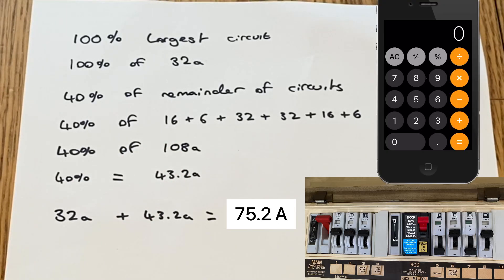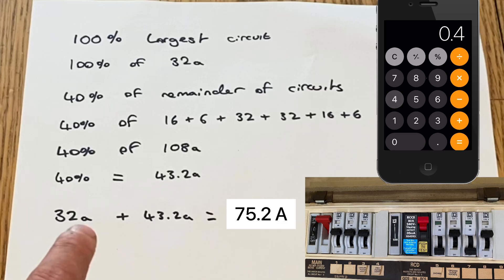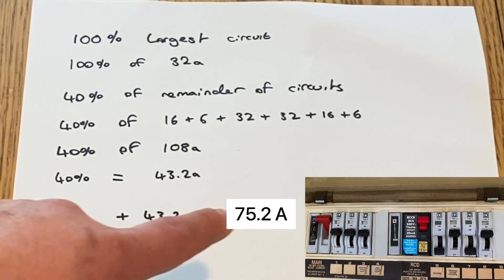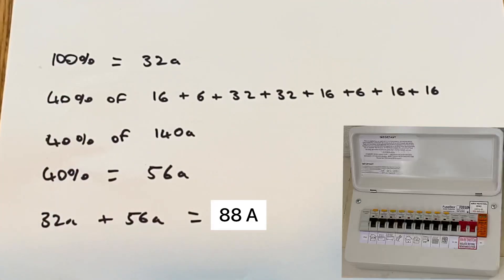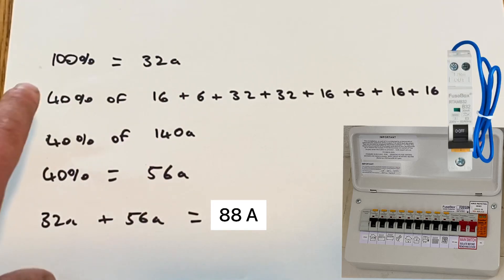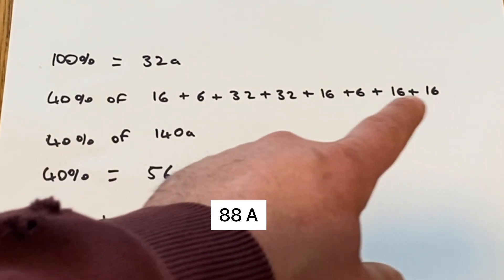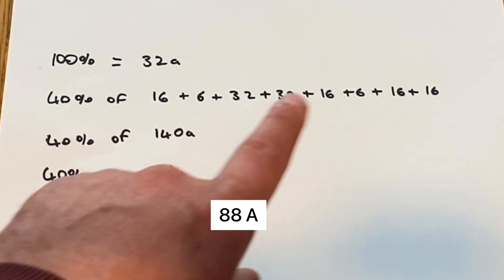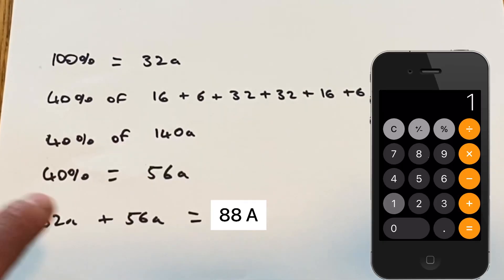For the new layout with the extra circuits, again we take 100% of the largest circuit, 40% of the remainder. Again we add all of these together, we don't add the largest circuit we've already took. 40% of 140 amps, which is what these equal to, is actually 56 amps.